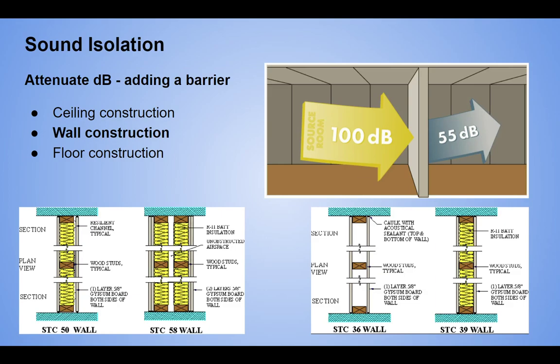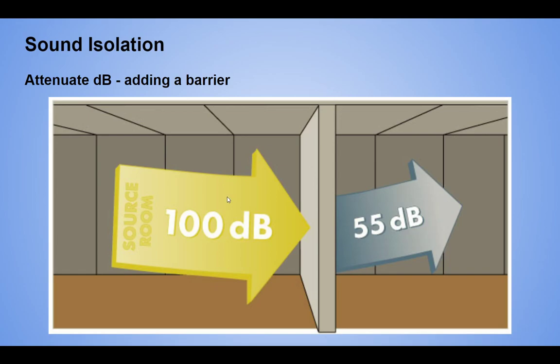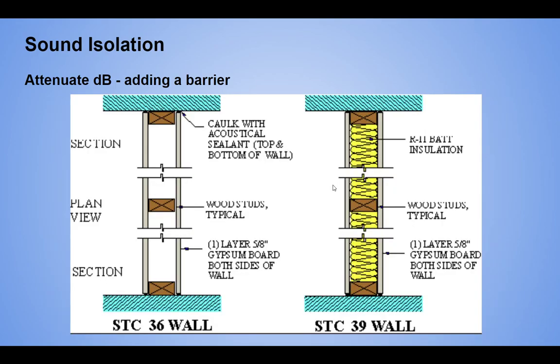In this instance we're just going to look at wall construction, using the diagram we've seen before: 100 dB source room, 55 dB on the other side — an attenuation of 45 dB. That's our goal. Remember the problem with single number descriptors: we don't know what that sounds like. Most likely this is 55 around 125 or 250 Hz. If this is 55 at 4k, we've got big problems — that means our NC on the other side is around 60, way too loud.